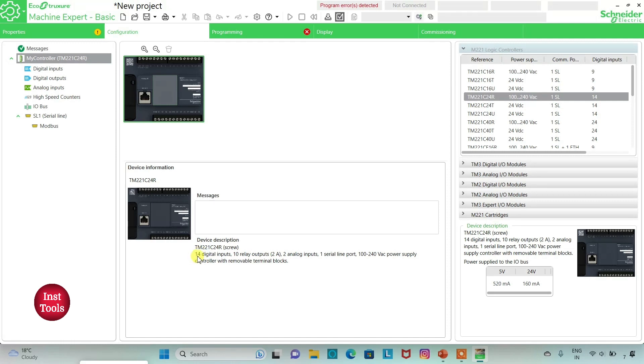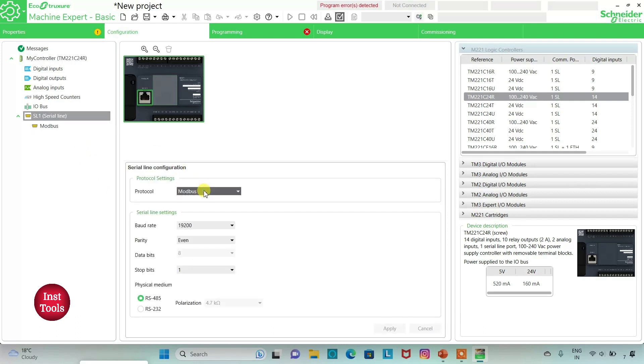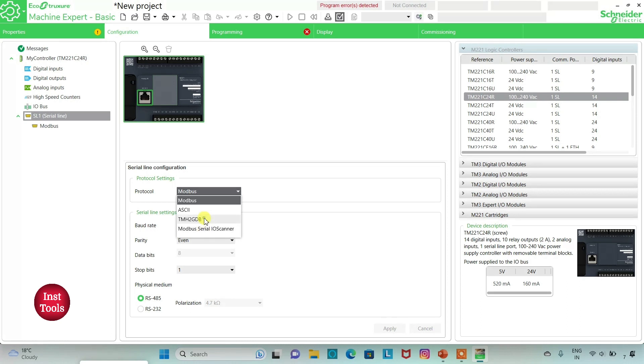The TM221C24R has 14 digital inputs, 10 relay outputs, two analog inputs, one serial line, and a 100 to 240 volt AC power supply controller with removable terminal blocks. I can also go to serial line and select the protocol as Modbus ASCII TMH2GDB or Modbus Serial IO Scanner. I will select TMH2GDB and click apply.